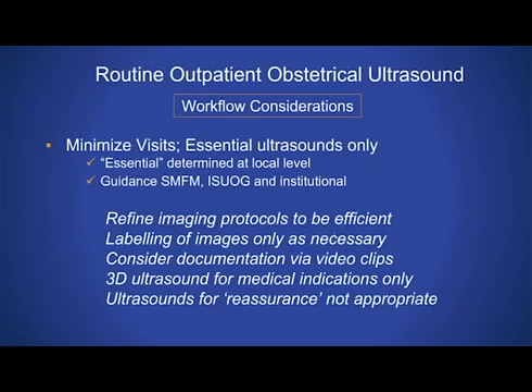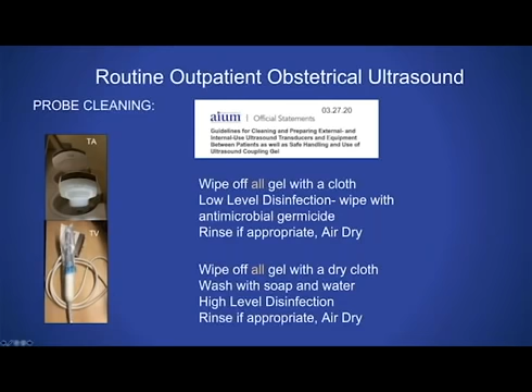We talked about probe cleaning, and the thing that I would like to underscore is that you really have to wipe off all the gel with a cloth. Now, with your transabdominal probes, we usually do that with the transducer still on the machine. We wipe off all the gel with a dry cloth, and then we do low-level disinfection with an antimicrobial germicide. You can see the CDC website or AIUM document that Oliver spearheaded, which will refer you to the appropriate germicides. And then you want to rinse if appropriate and air dry. If you can't get all the gel off, you really need to disconnect the transabdominal transducer from the ultrasound system and wash it with soap and water before you apply your low-level disinfection. And the same applies with your transvaginal ultrasound.